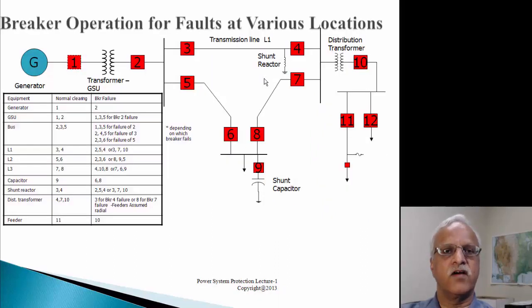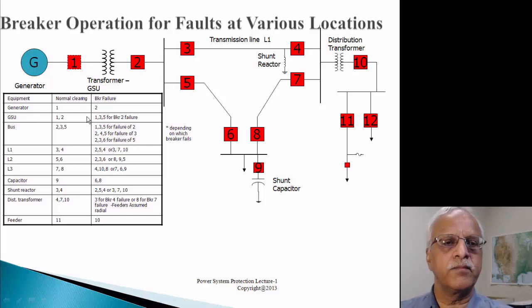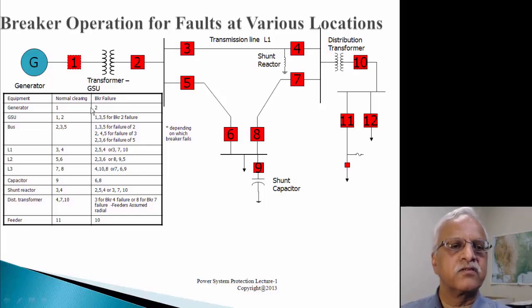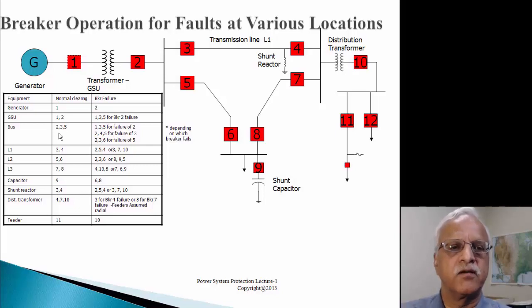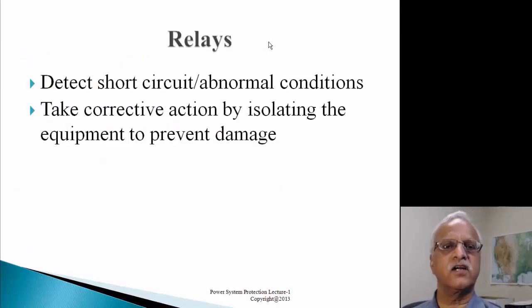Let's look at breaker operations for faults at various locations. For generator 1, we open breaker 1. For the GSU, we open breakers 1 and 2. If breaker 1 fails, we open breaker 2. For bus protection, we should operate breakers 2, 3, and 5. If breaker 3 fails, we send information to the remote end that breaker 3 failed for a bus fault, and we open breaker 4. The relays essentially detect short circuits or abnormal conditions and take corrective actions by isolating equipment to prevent damage.